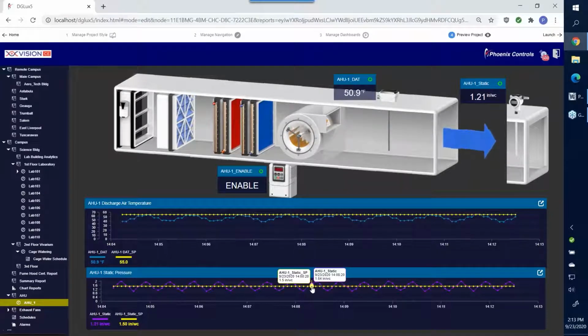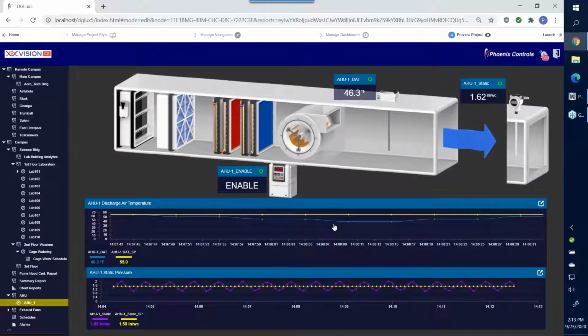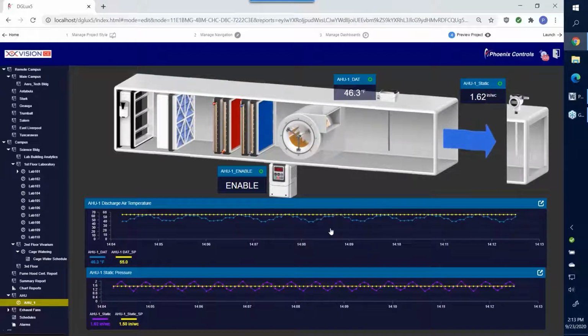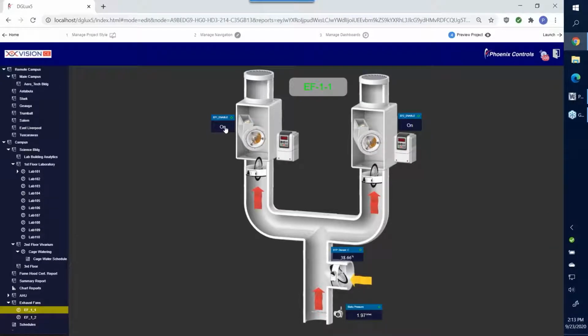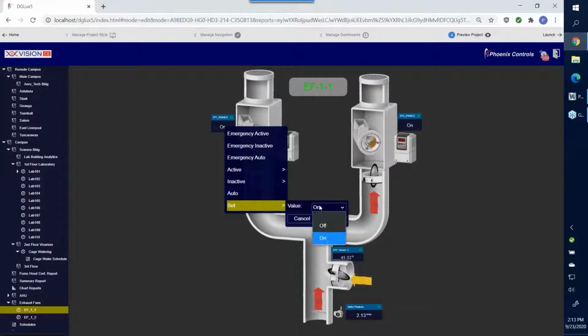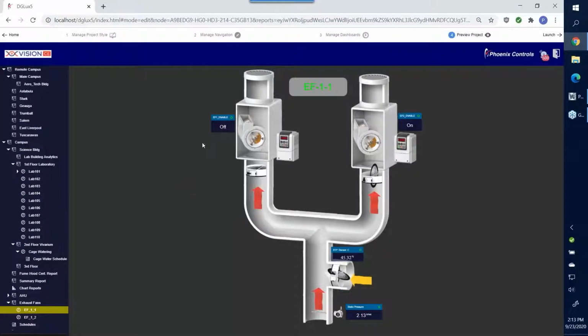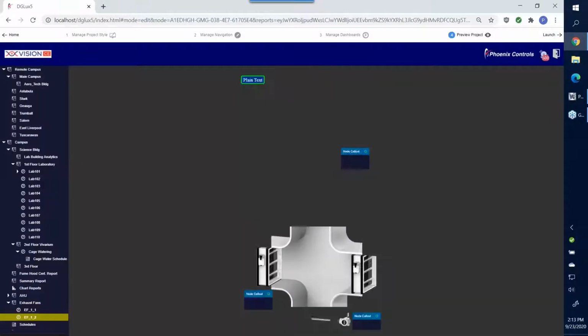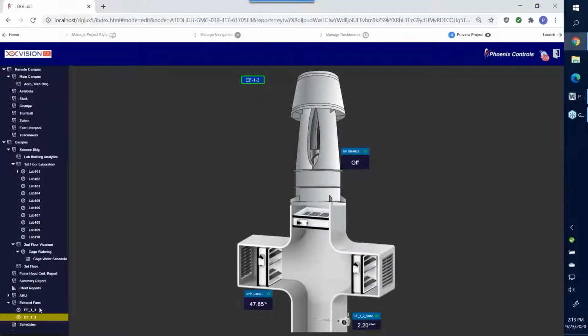We've never really been able to do that before, but now, due to the onset of being able to share information and install our own sensors to provide that type of feedback, it's an extremely useful tool so we can identify problems and help the facility manage these critical spaces in ways we haven't in the past. With air handling units and particular exhaust fan systems, we even have the capability to provide override to turn things off, open dampers, and create just about any sequence imaginable from these types of systems.